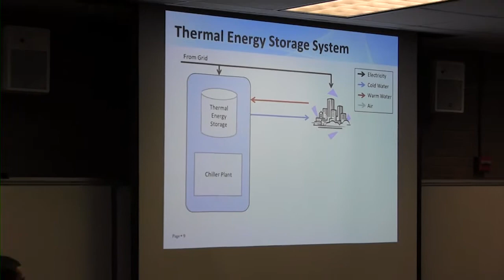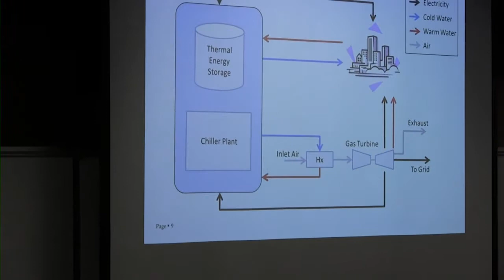When it gets really hot outside, natural gas turbines lose capacity because the density of air is reduced, so your mass flow rate through the turbine goes down and your capacity goes down. One way to mitigate that is by cooling the inlet air, drawing some cold water out, cooling the inlet air to around 40 degrees Fahrenheit, and sending it through the turbine. You get big boosts in capacity.